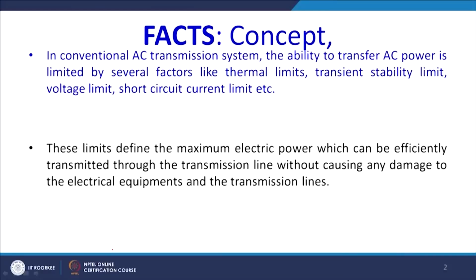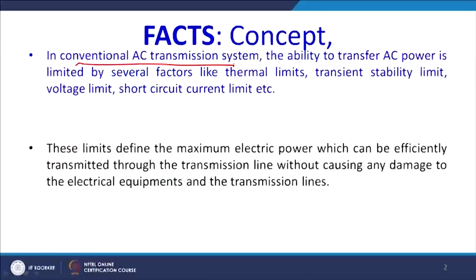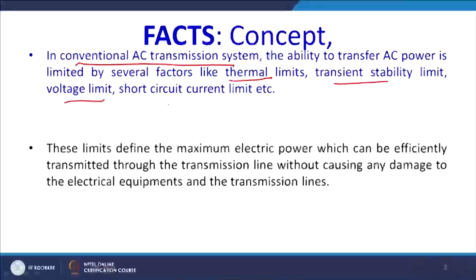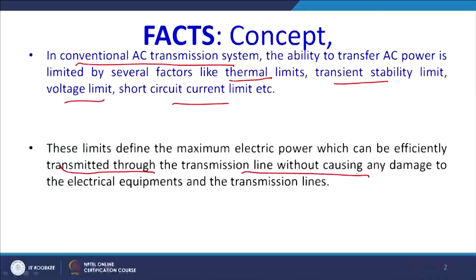As we have understood, the power transfer capability of conventional AC systems is mainly limited by a few constraints. These are the thermal limit, transient limit, voltage limit and short circuit limit, and these limits can be enhanced by FACTS devices. These limits define the maximum power that can be efficiently transmitted through the transmission line without causing damage to the equipment of the transmission line.